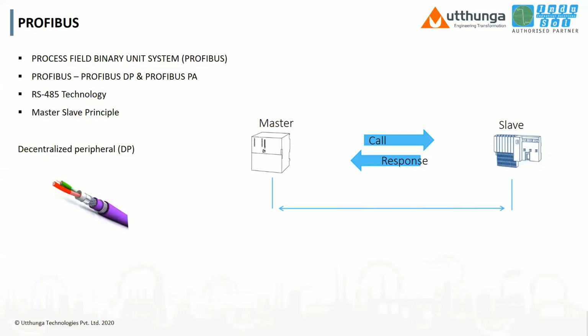While DP uses RS-485 technology, Profibus PA uses Manchester bus-powered intrinsic safety. So where safety is the utmost concern, we use the PA technology in hazardous areas. Both the Profibus technologies use the master-slave principle, where communication in the system happens when a master requests data and a slave responds with the data required.